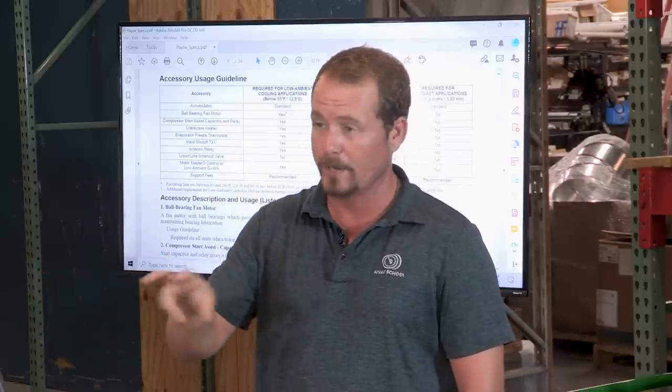So your motor acts as a generator. A motor is being turned by electricity, creating electricity, creating an electromagnetic field. But once that motor gets up and spinning, it actually has this responsive magnetic field that produces this additional potential. That's what we call back EMF or counter EMF. Okay, and that's why your voltage is higher.